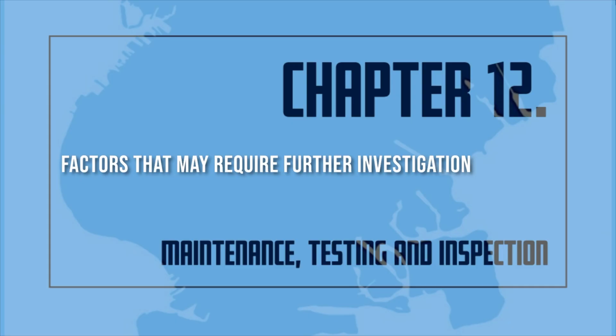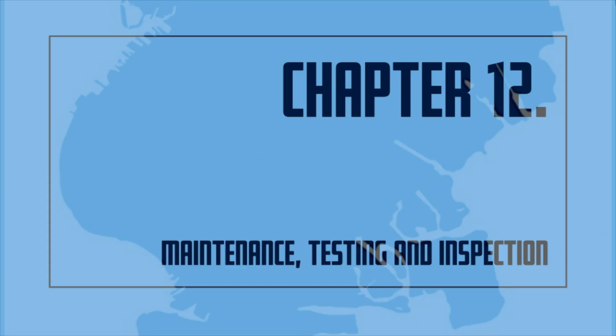Glass bulb sprinklers are sensitive to damage and are required to be shipped from the factory with protection. The orange caps and straps need to be removed prior to putting the system in service. The sprinkler will fail to operate with them in place.